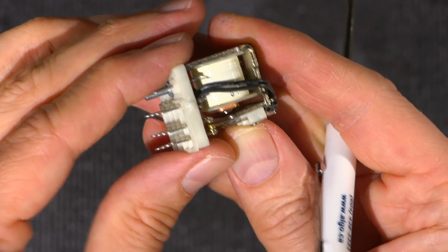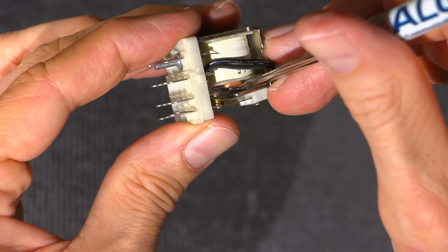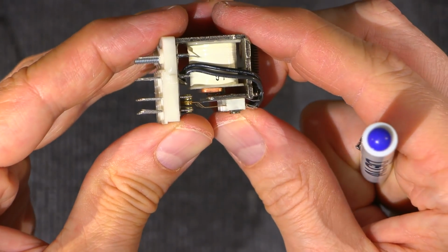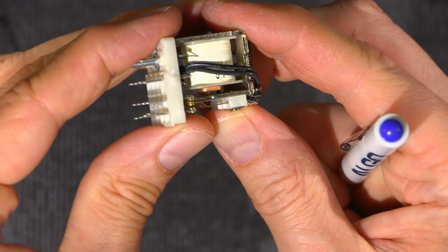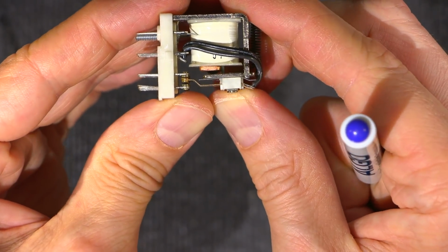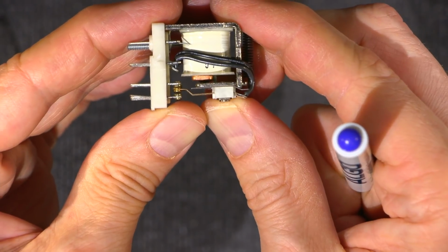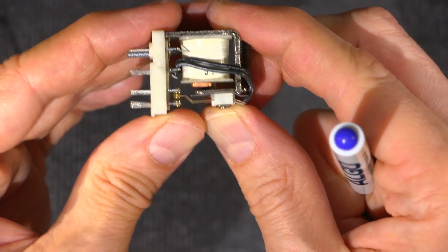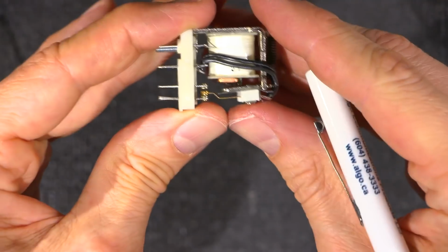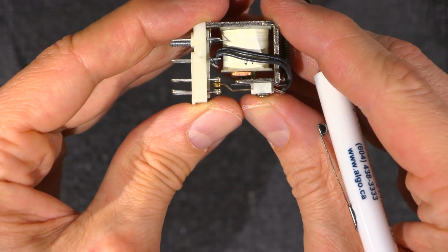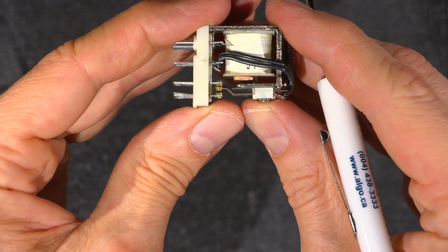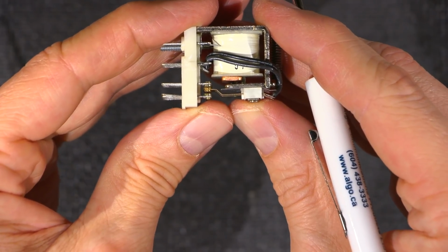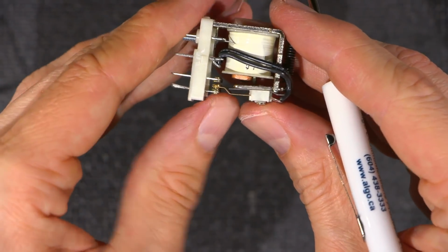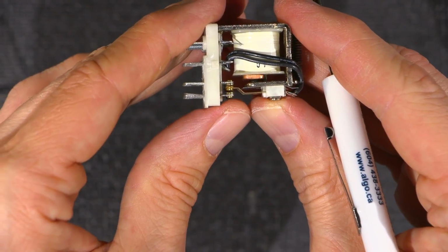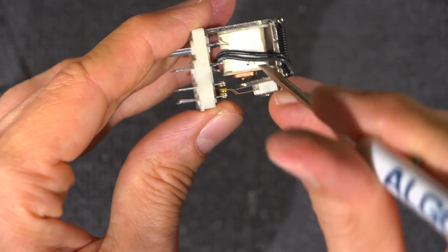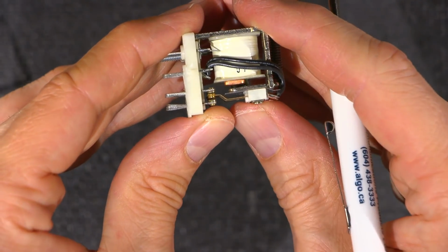Lots of space. Now, don't be confused by this. There's a little piece of the core sticking out in there. So it's already making contact there, but there's still a gap. And you can see me closing that gap. So it's making contact there. You can see the rest of that. Now, you can see as it's doing that, it's putting tension on the contact. You don't want these to just lightly touch like this and then it's closed. If you have to retension these contacts, you want to make sure that these touch before the arm touches the electromagnet, so that way there's tension on it.